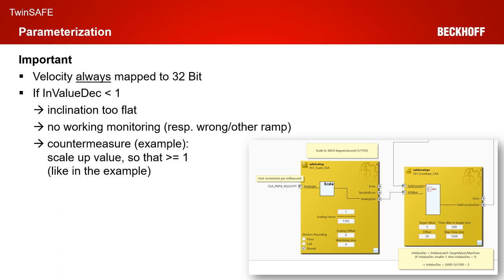That was the quick realization of an SS1 functionality with envelope monitoring. For the parameterization, a short summary: the velocity is always mapped to 32 bits, so even if the encoder only gives 24 bits for example, the value is shifted left so the lesser bits are zero and the upper bits always match the information — in our case a 32-bit integer value. When you calculate the scaling factors, for the envelope function block you always have to check the decrement for the input value. If that decrement is less than one, the inclination is too flat and you have no working monitoring for your application.